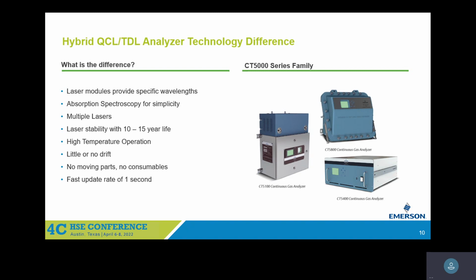Additionally, being able to measure multiple things, multiple analytes within one analyzer is advantageous, and so we can put multiple lasers in there. The laser stability, as I mentioned, we did a lot of work to make them very stable. So they run 10 to 15 years, and that's critical for the reliability of the analyzers. Reliability is critical to CEMS. They can also operate at high temperatures. At least the analyzer is designed to operate at higher temperatures.